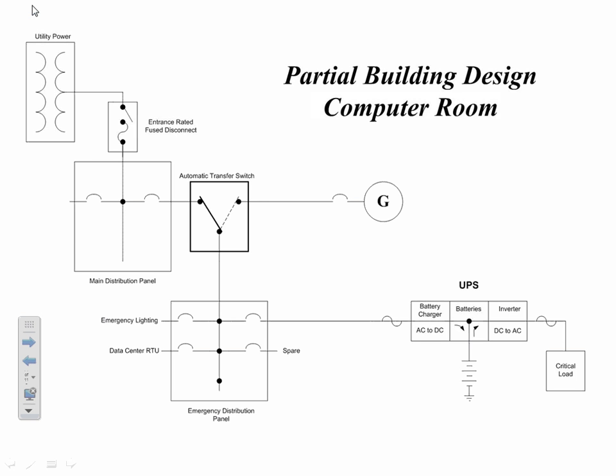So what happens now? The power fails. This is gone. The sensors here on the transfer switch see that. And at this time, this whole panel is dark because the power failed. But the critical load is still being powered out here because the inverter section of the UPS is still connected to the batteries. This sine wave is still there. Now, since power is gone here, the generator set is told to start, comes up to speed and frequency. Sensors here see it, transfer over to the generator set, and now we've repowered the battery charger down here on the UPS. So this is still totally operational. The UPS load, the critical load, has not been without power.